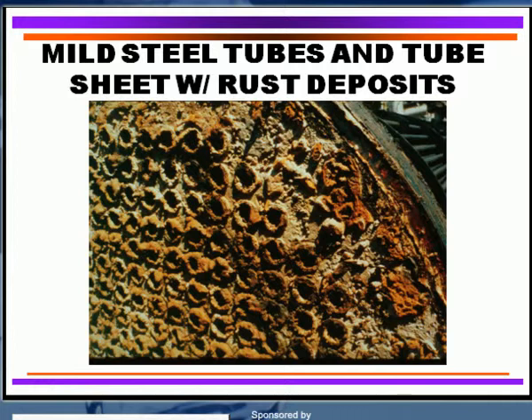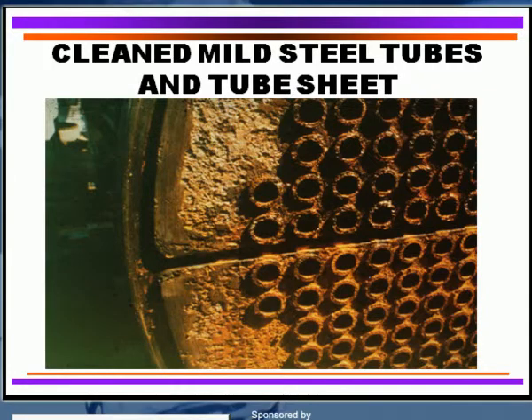The key here is that you are using the water from the cooling tower system to carry the inhibitors to the areas that need to be protected. If you have a barrier such as all this corrosion product, the inhibitor will never get to the metal surface. So you could even make it worse by adding a phosphate treatment program to a surface in this condition.